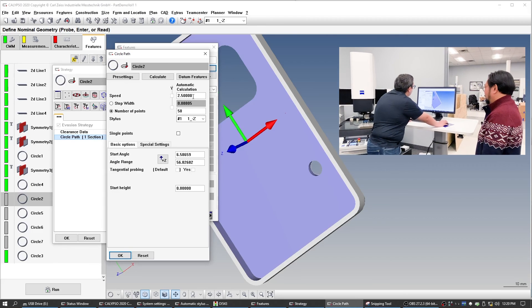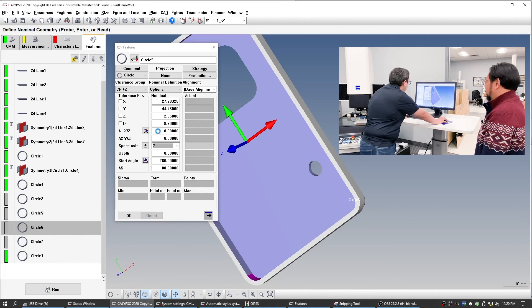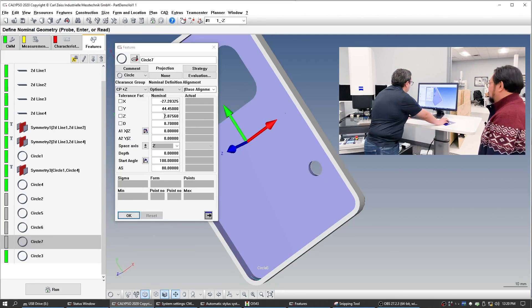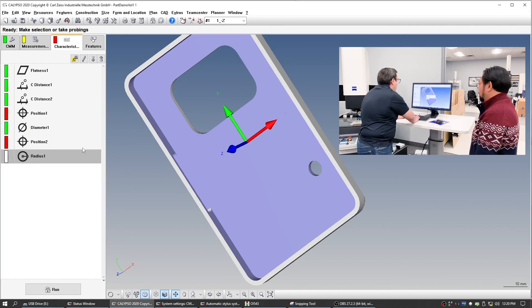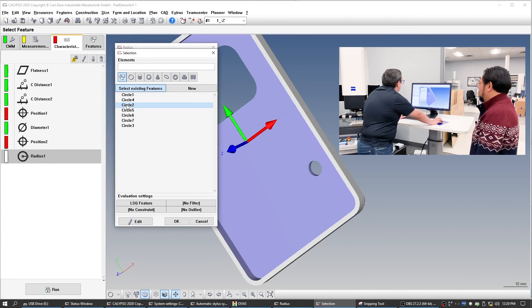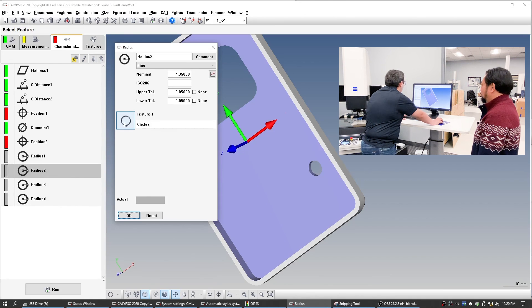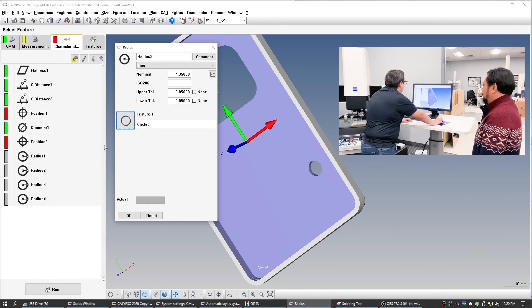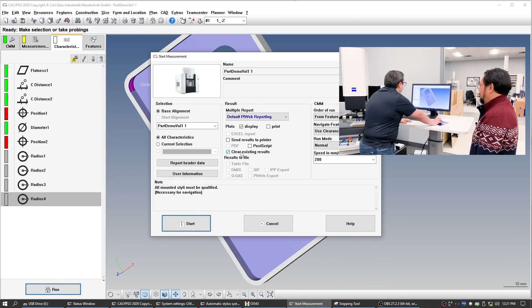Let's make sure that the strategy is fine. It's going relatively slow, which is good. 50 points — that should be enough to measure everything. So it looks like the only thing we really have to change is the Z height — just make them consistent. Consistency is important when you want to do runs and compare things to each other. And then let's add the radius to all of these. It really is easy to just go back and add it really quick — make sure it's in the right order. At this point it's just clicking the things you want to be measured.